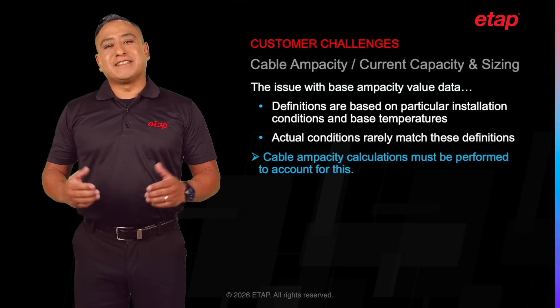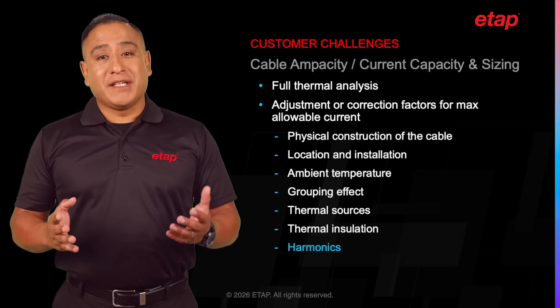These factors include, but are not limited to, the physical construction of the cable, such as the conductor material, diameter, layers, and thickness of the insulation, armor, sheath, bedding, etc. Location and installation of the cable: underground or above ground, conduits, trays, cable formation and spacing, etc. Ambient temperature, as it directly affects the heat dissipation. Grouping effect, quantity of cables, effect of thermal sources such as steam pipes, thermal insulation, harmonics, which cause additional rise in temperature, solar radiation, and additional adjustment factors.